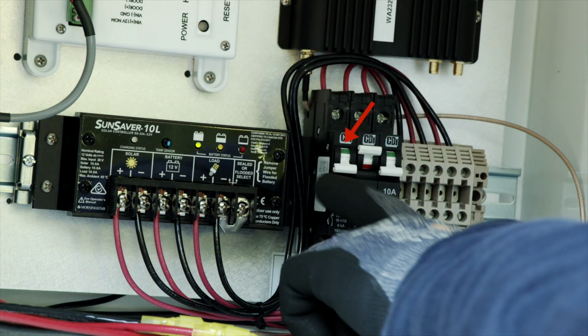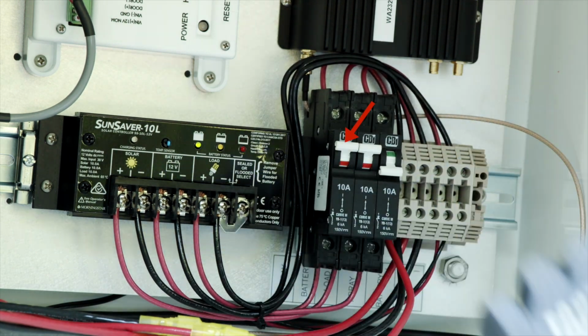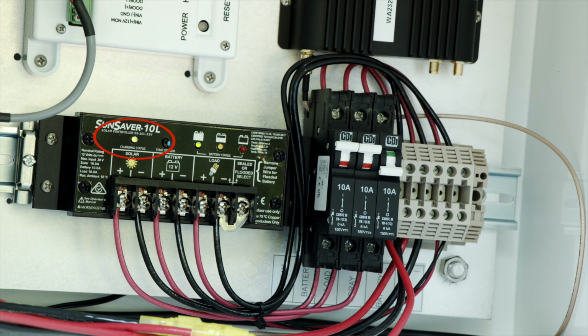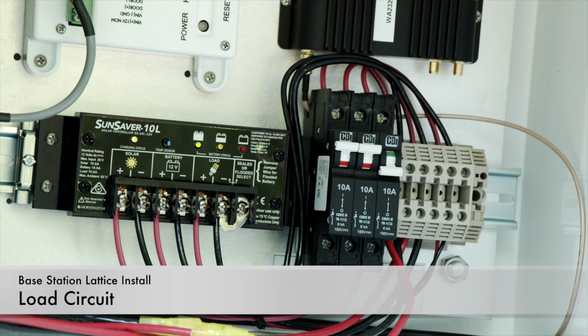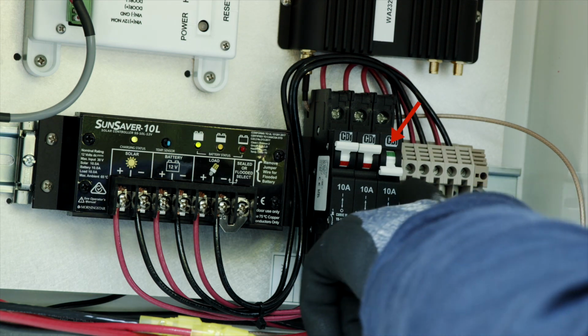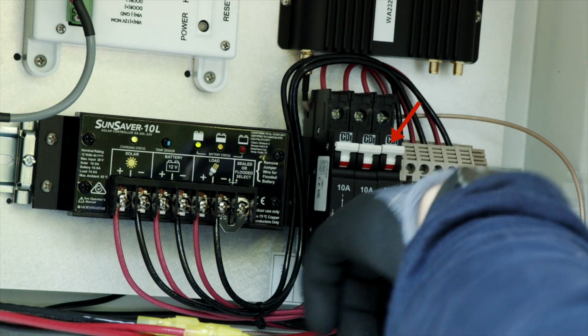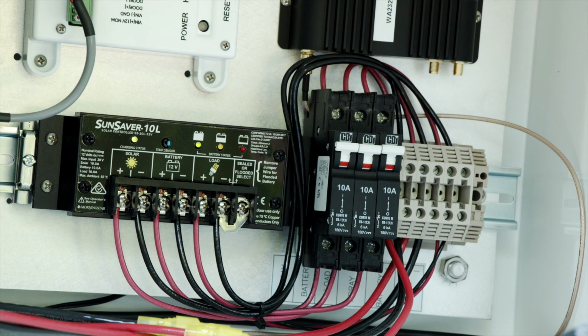Solar panel circuit. Switch on the left breaker, labeled as Array, for the solar panel connection. Wait for 10 seconds, allowing the solar controller to register. The charging status LED will be green if the sun is shining and charging the battery. Load circuit. Switch on the right breaker, labeled as load, to power on the electronics. It may take up to 5 minutes for the system to power up completely.